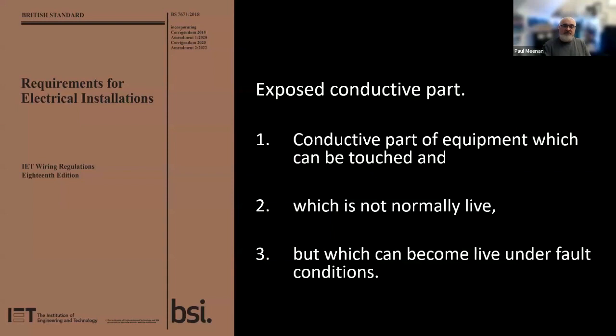Now, I adopt simple rules to learn this stuff, and I like the rule of 3. So what is an exposed conductive part? Well, in the wiring regulations there is a paragraph, but if you're an apprentice or a learner, get a highlighter pen. Highlight things, break the sentences and the paragraphs up so that you can break it down into simple stuff. So an exposed conductive part is a conductive part of equipment which can be touched. Okay, but it's not normally live. Fine, but it can become live under fault conditions. Three parts to that, a very simple rule to remember for an exposed conductive part. It's a part of equipment which can be touched, it's not normally live, and it can become live under fault conditions.